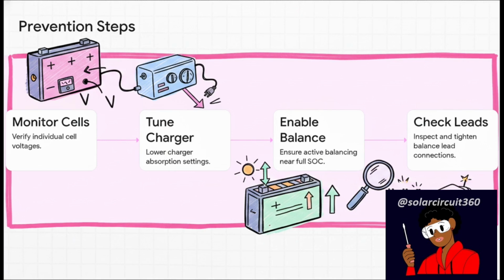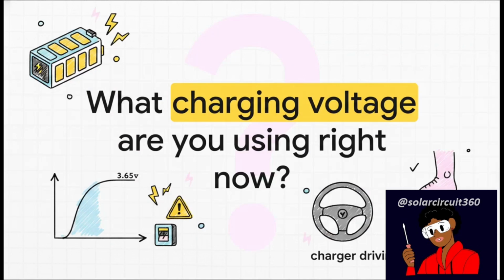First, always prioritize individual cell-level monitoring, never just trust the overall pack voltage. Second, adjust your charger's absorption settings downward so it finishes the charge and stops smoothly, long before any single cell gets close to that 3.65-volt emergency threshold. Third, ensure your system has sufficient active balancing that kicks in right near the top of the charge, which is exactly when those cells start drifting apart. And finally, visually inspect and physically tighten all your balance leads, a single loose sense wire can easily trick your BMS into a false overvoltage reading, shutting you down in an instant.